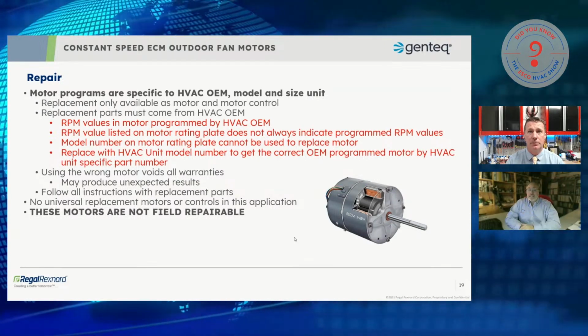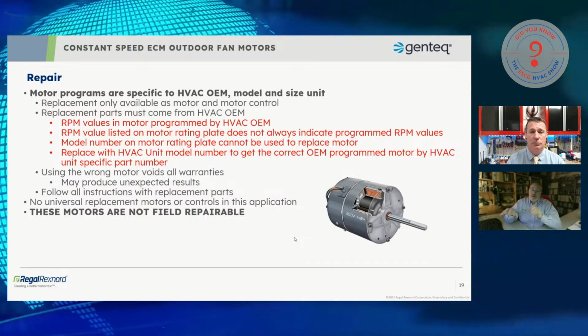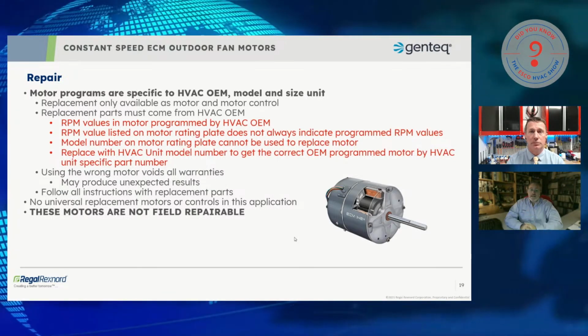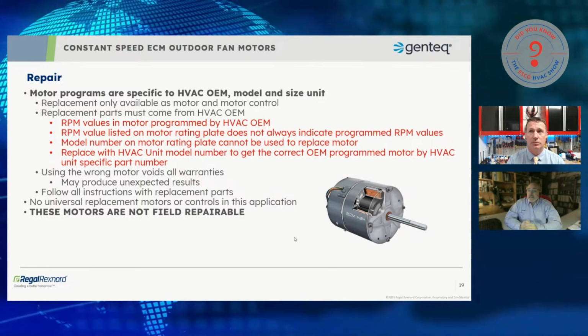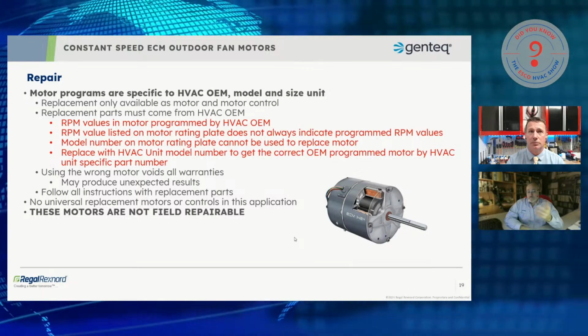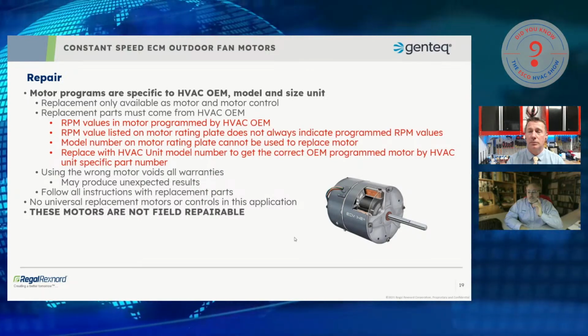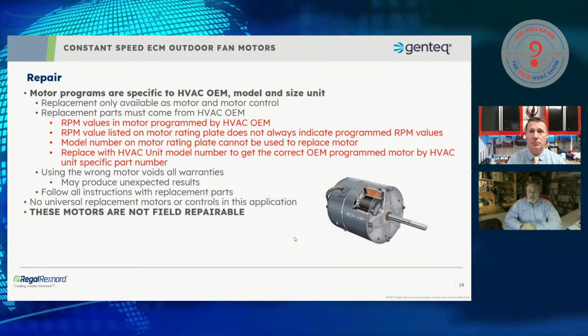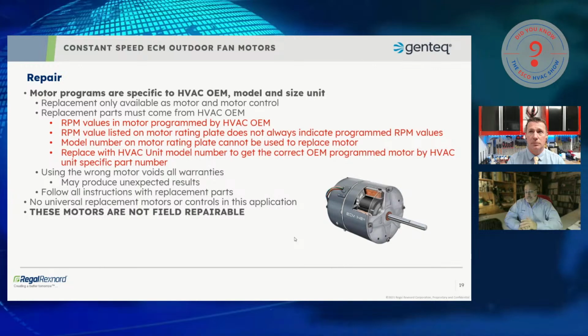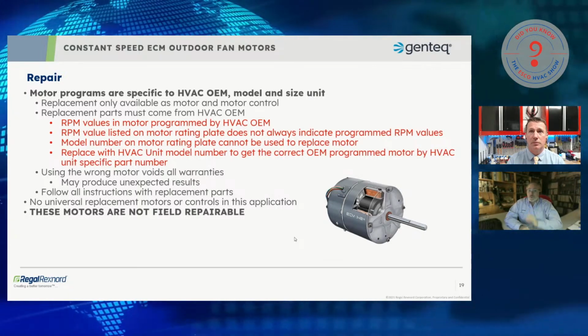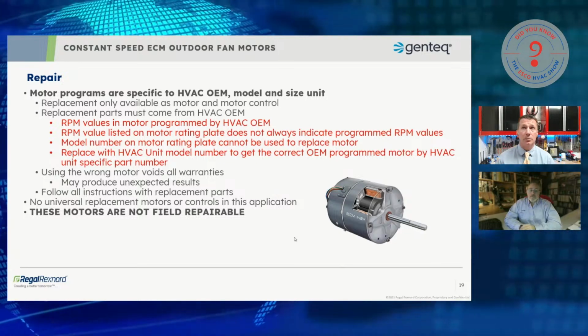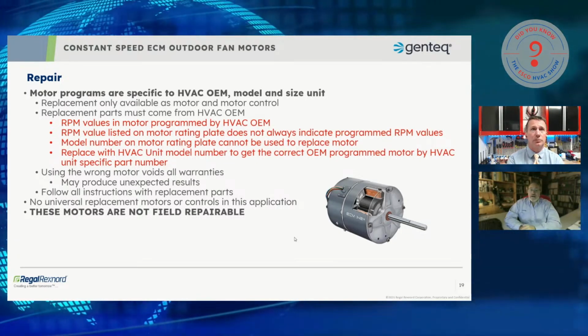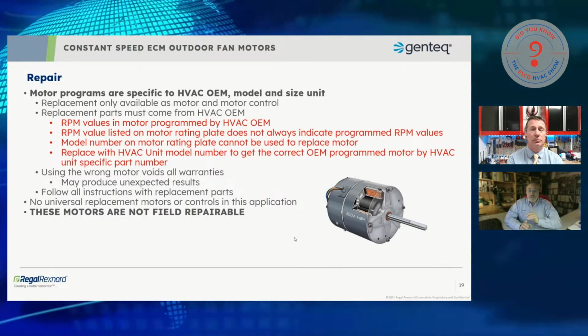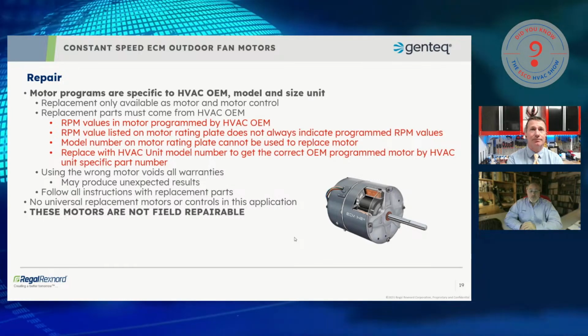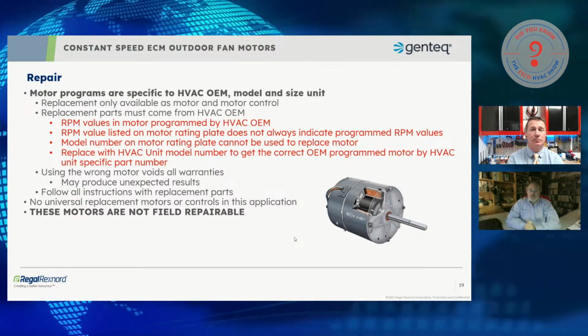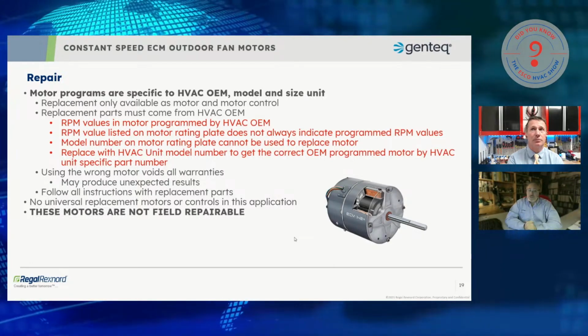So if you have a failed ECM outdoor fan motor and you want to get exactly what was there, plug for plug, plug and play, operating exactly like the original motor, you do have to go back to the OEM. And the biggest challenge, again, we brought this up a little bit earlier, but I do want to revisit this: the RPM on the rating plate of the failed OEM outdoor motor is not always, and in many cases not going to be, indicative of the programmed operating point or operating points of that motor. Yeah, makes sense completely. It may say 850 or 1075 on the side of the motor, but that may be one of the operating points. What's the first stage or operating point? Or maybe that 850 was how it was tested, and the manufacturer is choosing to run it at 950 and 1000. You just don't know.